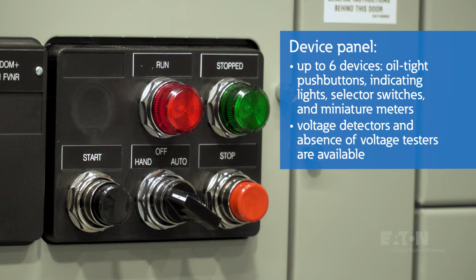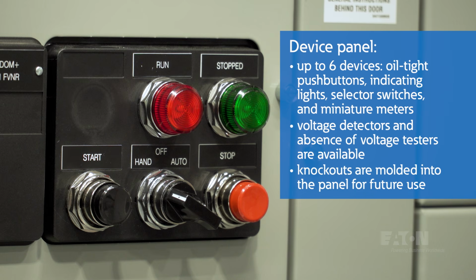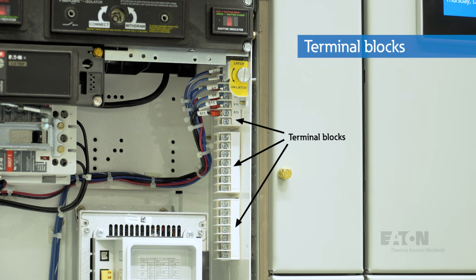Voltage detectors and absence of voltage testers are also available to be installed on the device panel and allow the end user to improve lockout-tagout procedures. Molded into the panel are knockouts to help with future additions of devices. Terminal blocks are mounted in knockouts on the vertical wireway side of the bucket, affording greater access to the unit compartment and its interior components. The 2-piece terminal block snap locks together to ensure permanent circuit continuity.